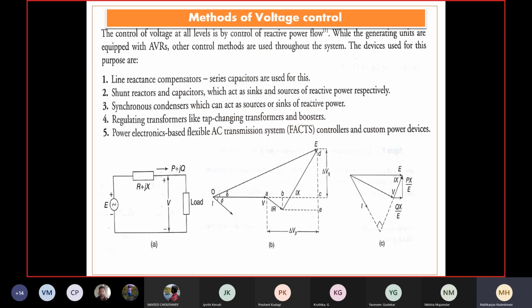So this is a synchronous machine based approach which is presently a very costly mechanism. It is the oldest mechanism because it involves a rotating machine absorbing power from the grid, running without any load on the shaft. Only the excitation control you are managing to compensate the required reactive power of the system. Hence it is costlier, but still it is in practice. And the other is regulating transformers like the tap changer and booster transformer.